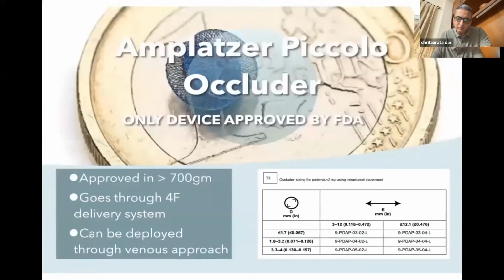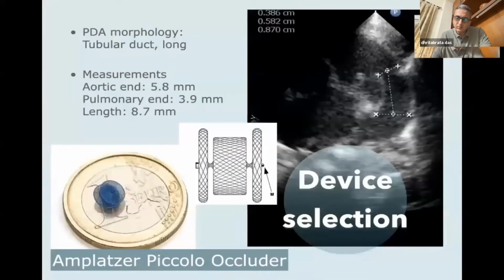Now, the Amplatzer Piccolo occluder is the only device approved by the FDA for use in such a small baby. It is approved for babies of more than 700 grams. The advantage is that it goes through the 4 French delivery system, and with a venous approach only, it is possible to deliver. This is the guide for choosing the device size depending upon the internal diameter at the narrowest point and the length of the ductus.